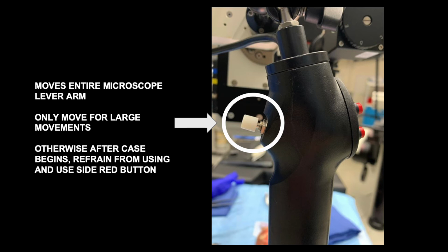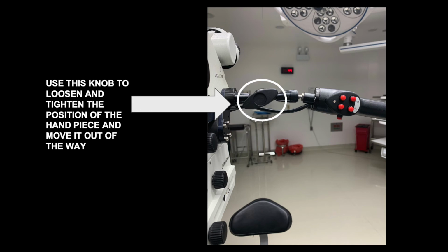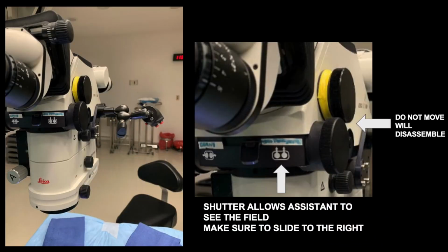And there's a knob that you could use to loosen this handle, this handpiece, move it out of the way and tighten it so it is completely out of your way and you're only using your non-dominant hand side handpiece. Again, there's a couple knobs that we don't want to touch or they will disassemble, but there is a shutter beneath the lens that allows your surgical assistant to see the field. So you want to make sure to slide it to the right, and so the arrows are pointing towards your assistant. So it ensures that your assistant can see what you're seeing in the surgical field.